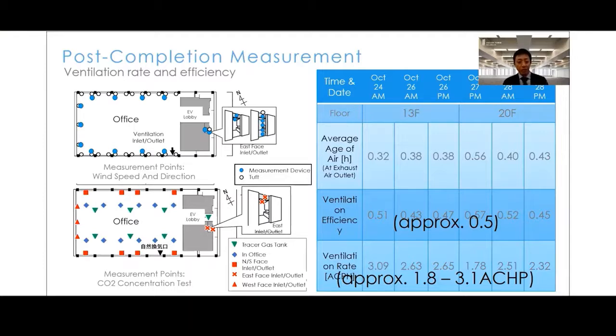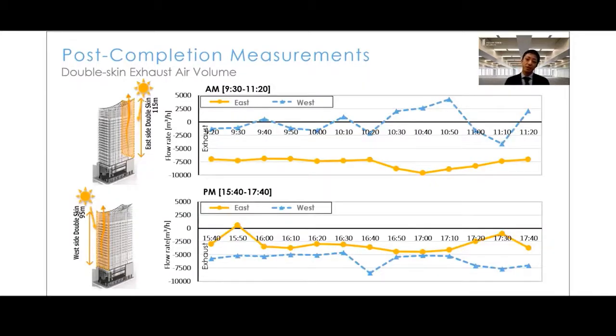The result was equivalent to the assumption made during the design, and also equivalent to the ventilation rate regularly designed for a mechanical system. The measurement also proved the stack effect of the double skin facade. As shown here, the exhaust air volume transition follows the sun path, with greater volume on the east side during the morning, whereas the exhaust at the west side becomes larger in the afternoon.